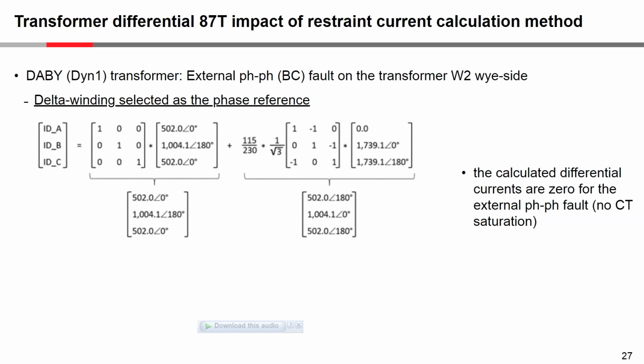So now what I have here is an external phase-to-phase fault on the same transformer, an external phase-to-phase fault on the winding 2 side. The fault is BC, so these are the winding 2 side currents there on the right, and I calculated the requisite currents that would be flowing on the winding 1 side.